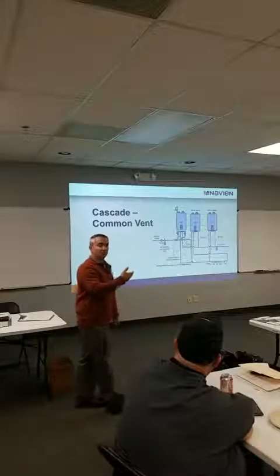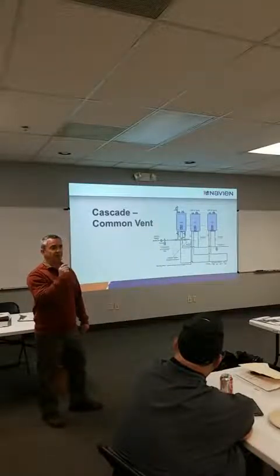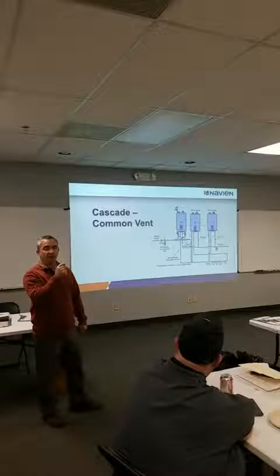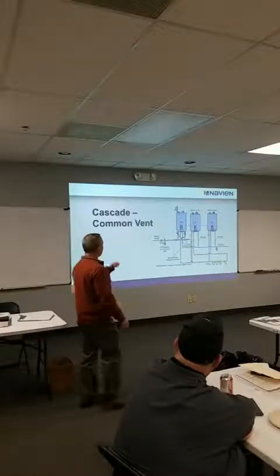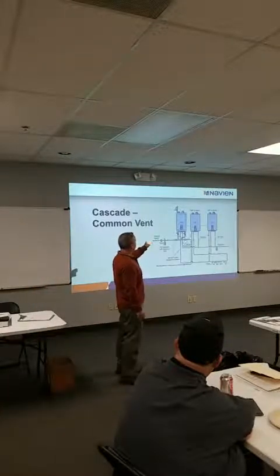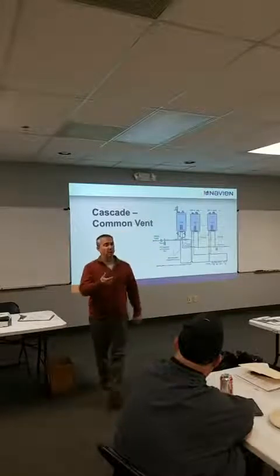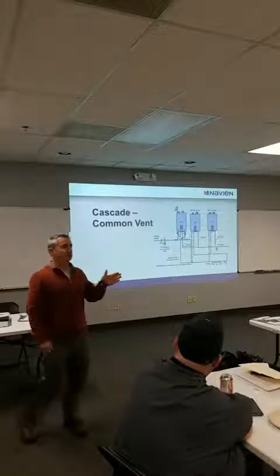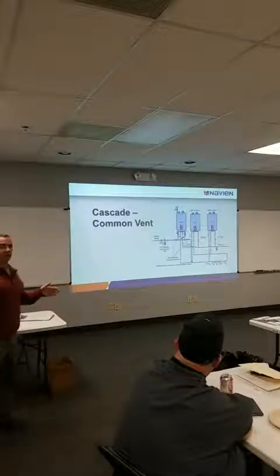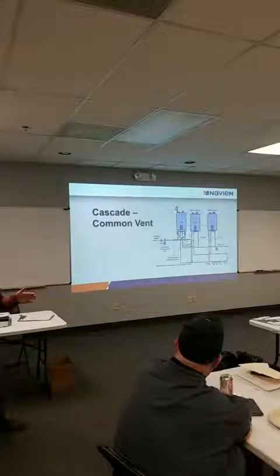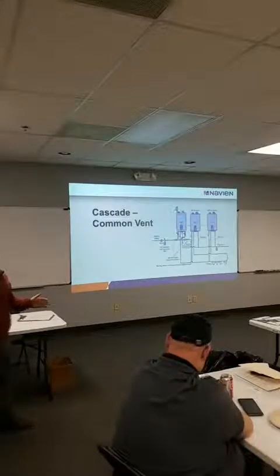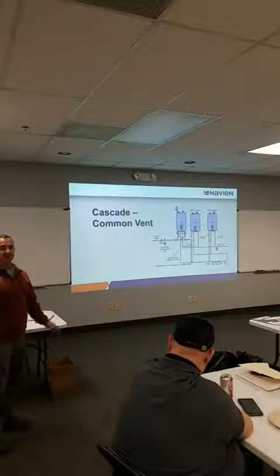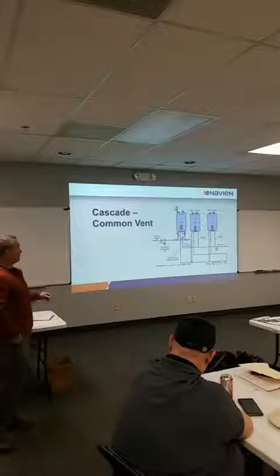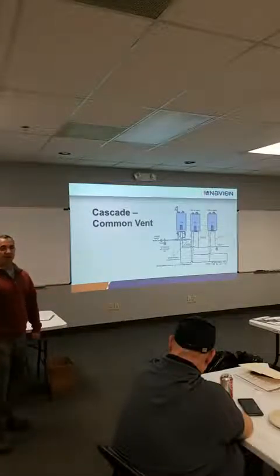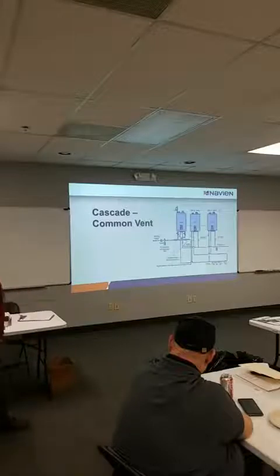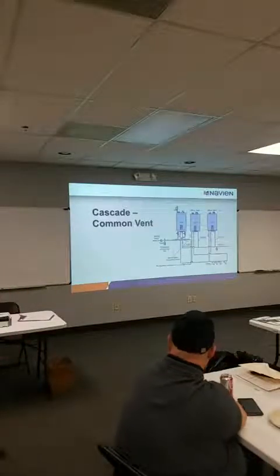cascade in tankless water heaters. We use the same damper kit with the communication cable. We always set the combi up as the main unit, and then we program in the water heaters. When we do that, the combi becomes your primary boiler, and the water heaters, regardless of how many you put in, become your primary water heaters. When those water heaters can no longer keep up with the domestic demand, they send a little signal over to the combi, which rolls that valve and backs them up on the domestic side. But other than that, it just takes lead as heat. That's correct. That's all it's doing is heat.